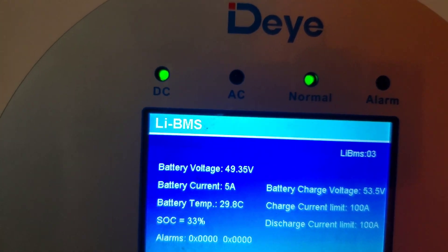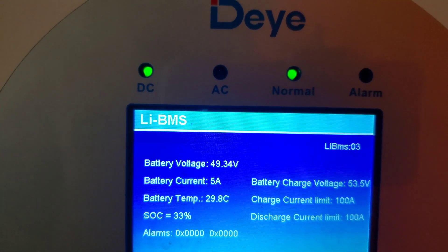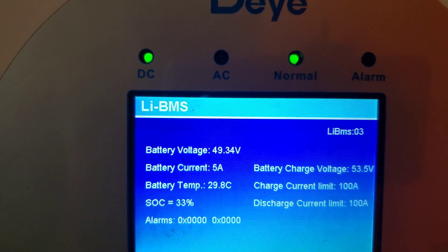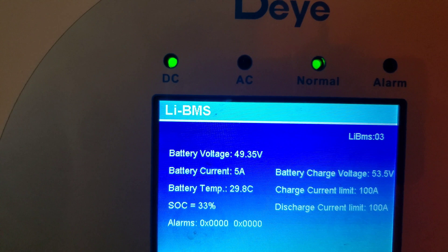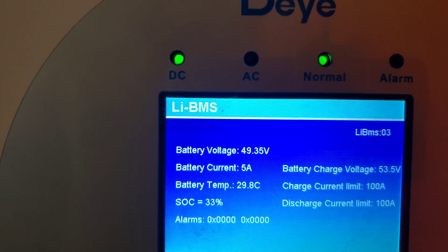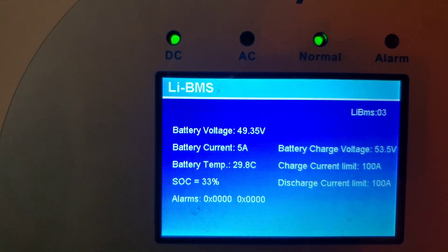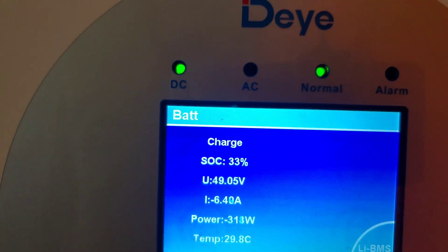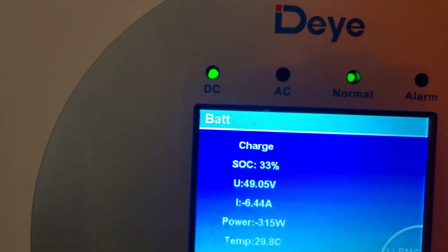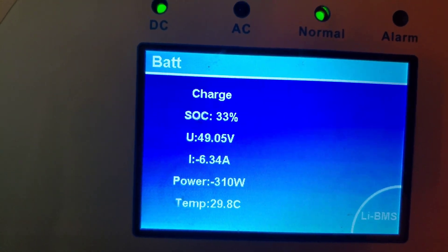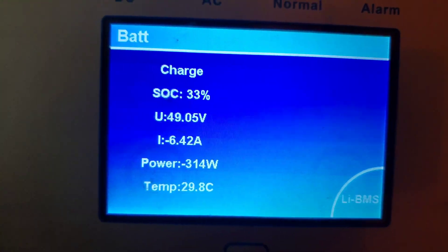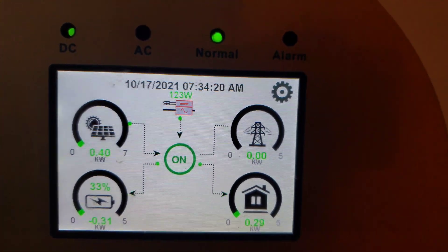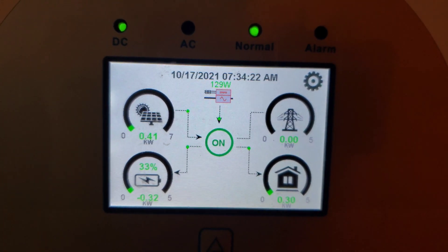The BMS battery current right now is 5 amps. 5 amps times 50 volts is 250 — well, a little less: 5 times 49 is about 245 watts. That's what the BMS is showing, and here the Deye is showing 313 watts. So the BMS data is different from the data we're seeing on the inverter. I did the math in my head so if I'm incorrect please let me know. If anyone else is experiencing this with the Deye, please post your comments and I'll contact Deye and ask them how we can correct this.